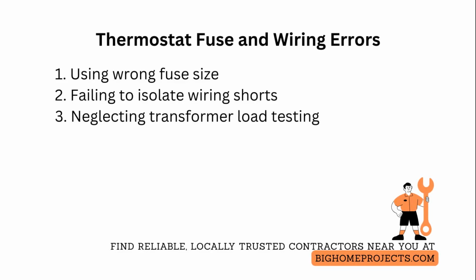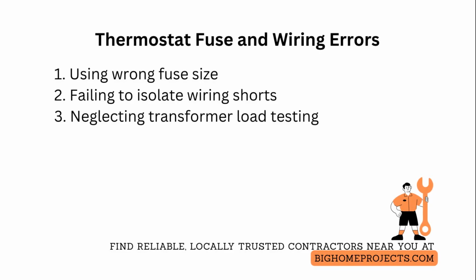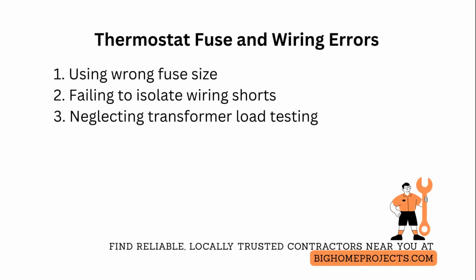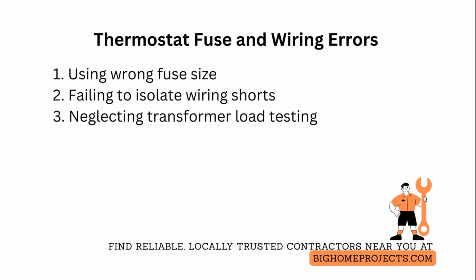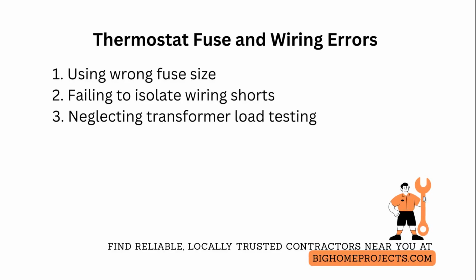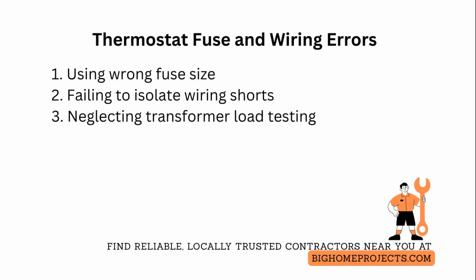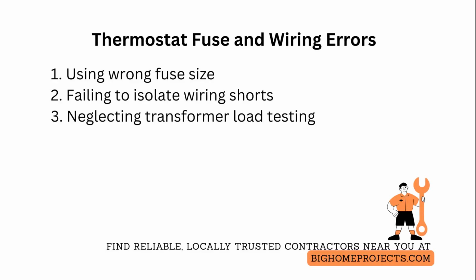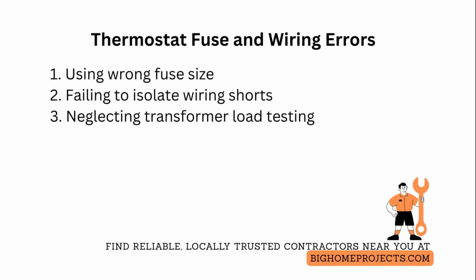Search terms include thermostat wiring short and transformer shorted. So methodically disconnect thermostat leads, test continuity, and inspect insulation to find and repair the fault before reinstalling a fuse. One of the other frequent errors is neglecting transformer load testing. People search transformer voltage drop and weak transformer symptoms. So measure open circuit and loaded secondary voltage, verify current draw with a clamp meter, and replace the transformer if it cannot maintain rated voltage under normal load.